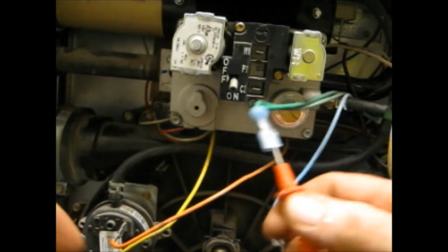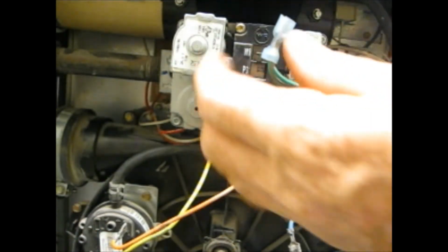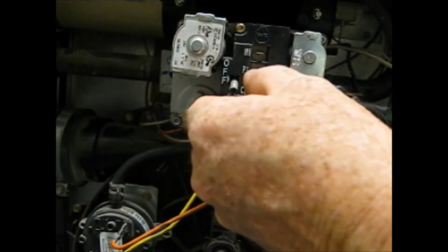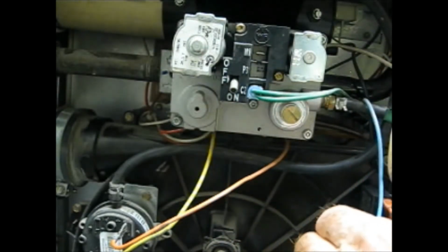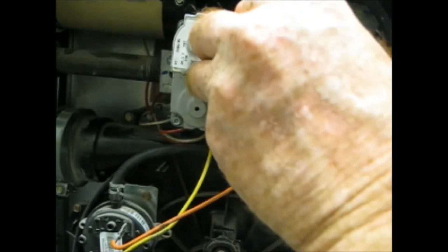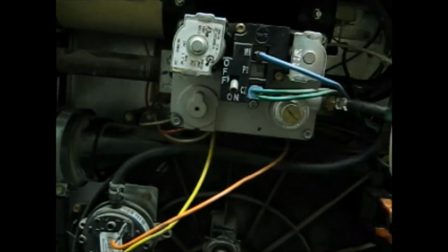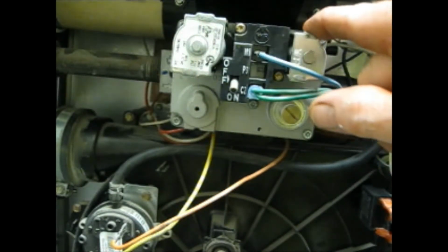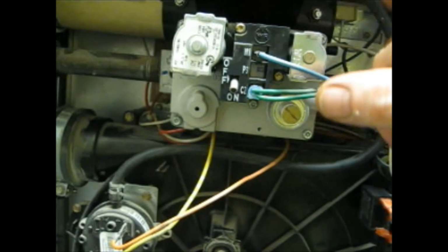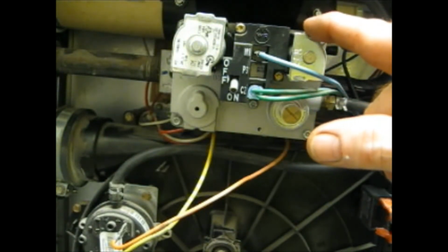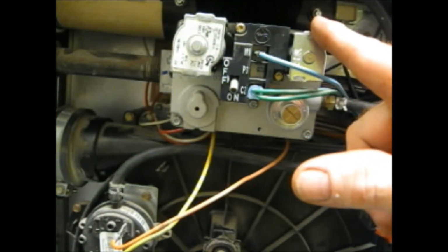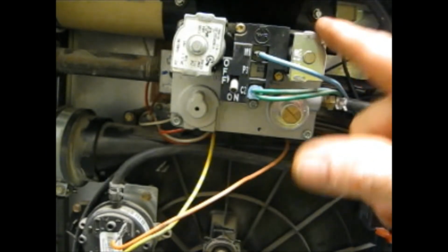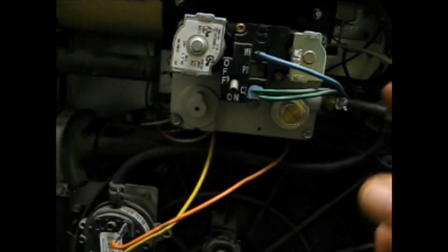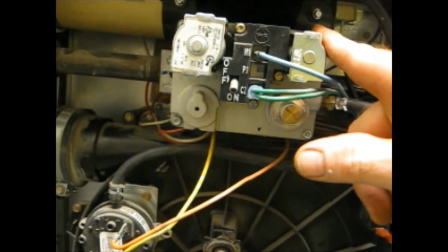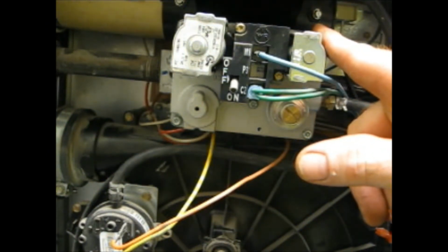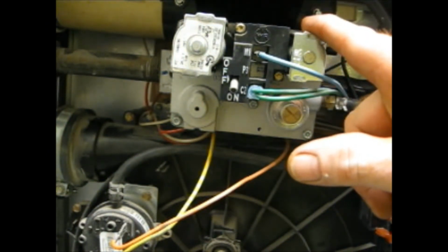Now, if we have power going to the gas valve, but nothing ends up happening, then that would tell us that the gas valve would be bad. Now, gas valves are a little bit more complicated to replace. If I had a bad gas valve and didn't know how to replace them, I'd probably call for a service call, because a gas valve is not only part electrical, but it also has some plumbing issues coming into it. And if you're not familiar with that, that might be something you might want to call a technician on.